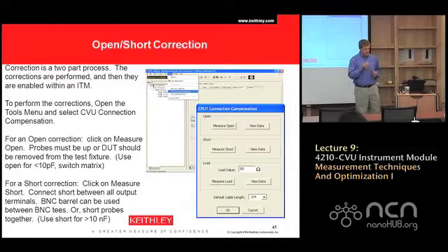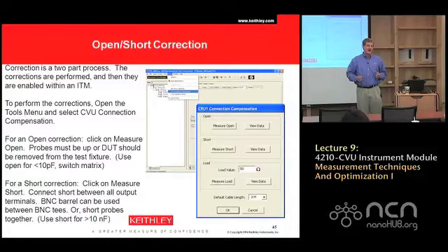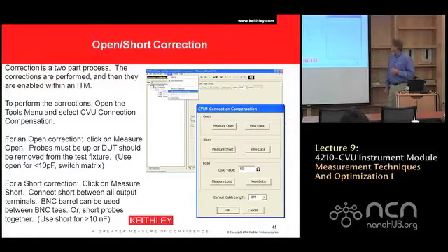So we chose to go 10 frequencies. Our research showed that, in general, 99% of the time that's more than enough frequencies for everybody, but it gives us 100% correction capability. Now, I'm thinking it takes 30 seconds to run a measure open. When you click the measure open button, it takes about 30 seconds to run every frequency and every range that we have. I can't remember for sure.